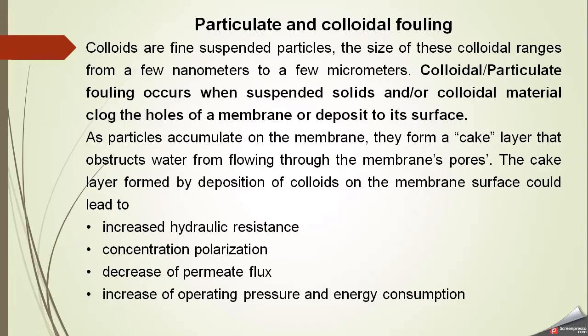The third type is particulate and colloidal fouling. Colloidal particles are fine suspended particles whose size varies from nanometers to a few micrometers. Colloidal or particulate fouling occurs when suspended solids or colloidal material clog the holes of the membrane or deposit on its surface. As particles accumulate on the membrane, they form a cake layer that obstructs water from flowing through the membrane pores.